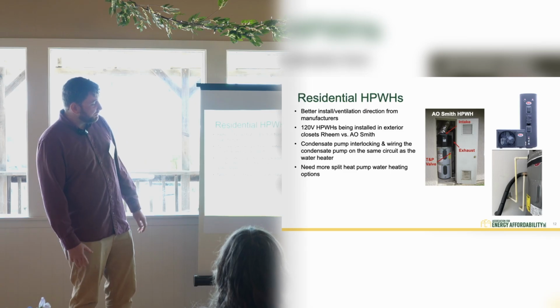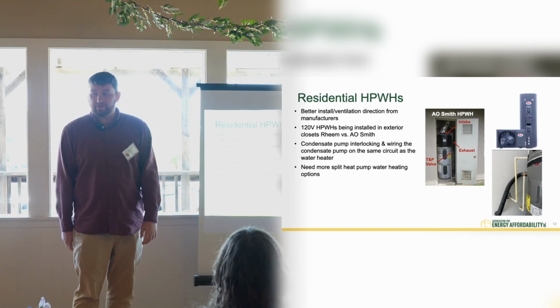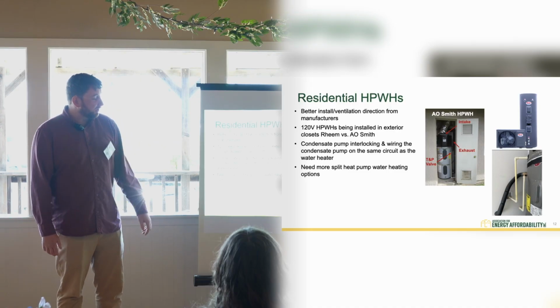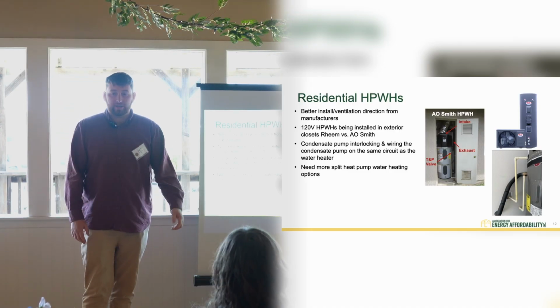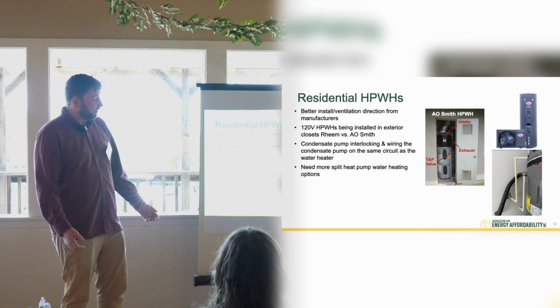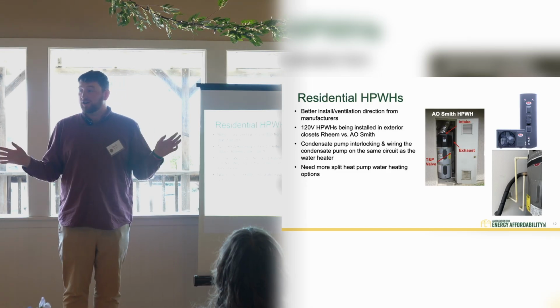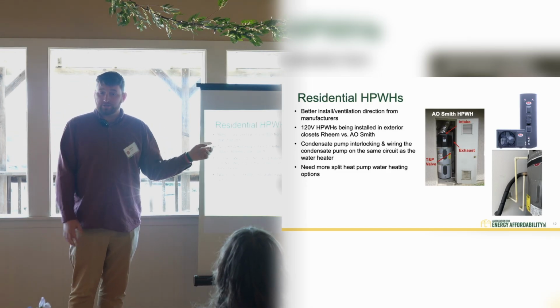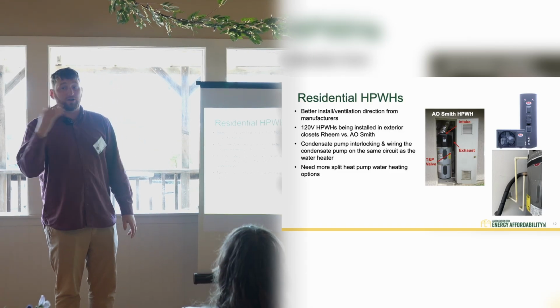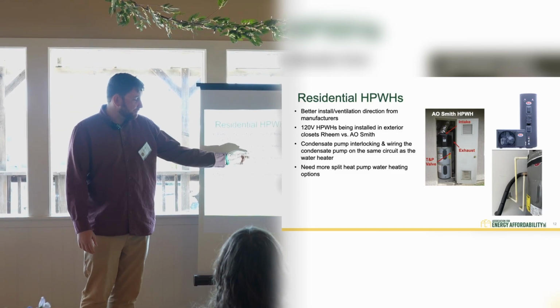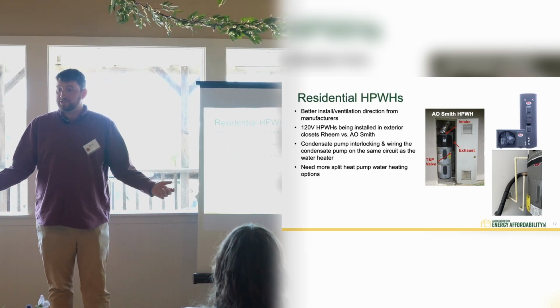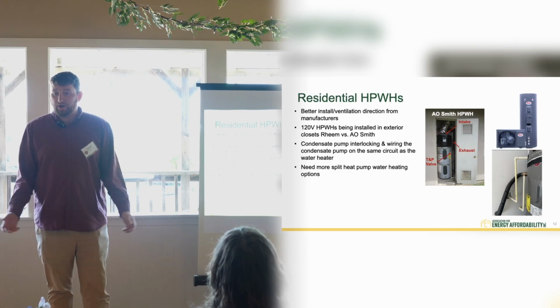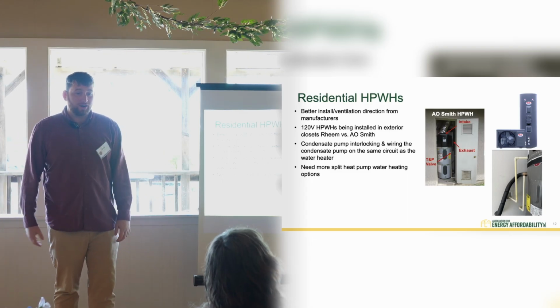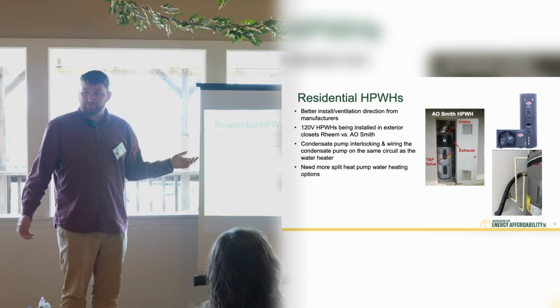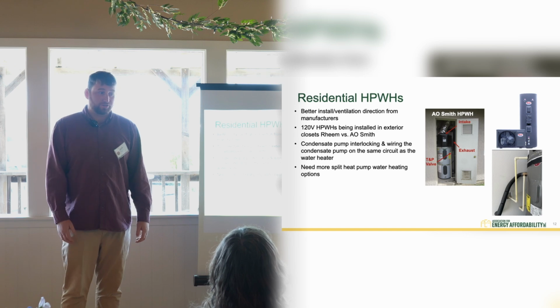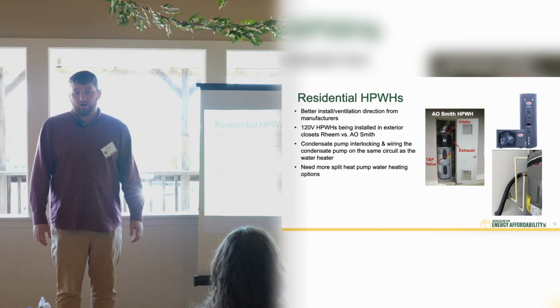This is really interesting. 120 volt heat pump water heaters being installed in exterior closets, Rheem versus A.O. Smith. When I call Rheem and tell them that their 120 volt heat pump water heaters that are shared circuit or dedicated circuit are being installed in exterior closets, they go, ooh, that's not a good idea. No literature ever anywhere that they say that you should not install these in exterior closets. Actually, some of the literature seems like they're recommending exterior closets. Whereas the A.O. Smith 120 volt shared circuit, it has electric resistance backup. And so it can be installed in exterior closets. But there's no literature that says that it has that 900 watt electric resistance backup. So if we're going to install these properly in buildings, we need better information from the manufacturer so that we don't screw it up and we don't have people running out of hot water on the coldest day of the year.